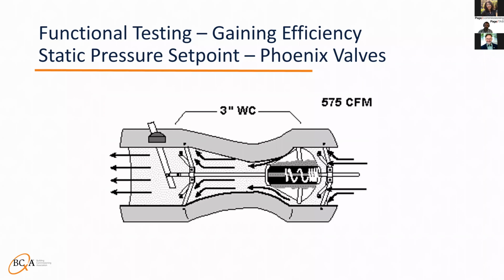TAB will need to read each one, or at least the units at the end of the run, and lower the static at the AHU until the differential pressure across the valve is just above its minimum. Obviously, you will want to put a buffer in there to avoid nuisance flow alarms. A good balance company would request a trend on that flow alarm for at least a week to verify the set point is correct.